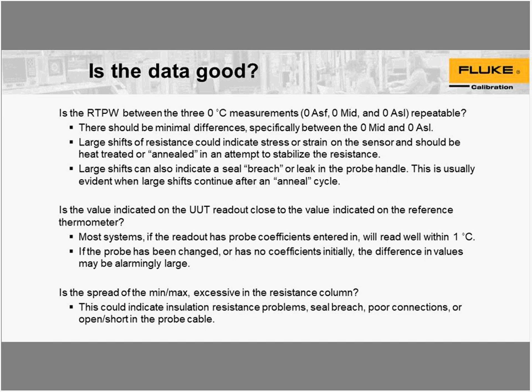So again, if the 3 measurements are repeatable, if they are, great, awesome. There should be minimal differences, specifically between the 0 mid and the 0 as left. The main reason is because when you're at the high temperatures, there is a slight possibility of a slight anneal. Okay. And that's why you're always looking at the mid and as left. That small shift should happen, and that's where everything should run. Large shifts of resistance can indicate stress or strain on the sensor and it should be heat treated or annealed. If your as found and your mid are that far or more apart, you probably should run that through an anneal.